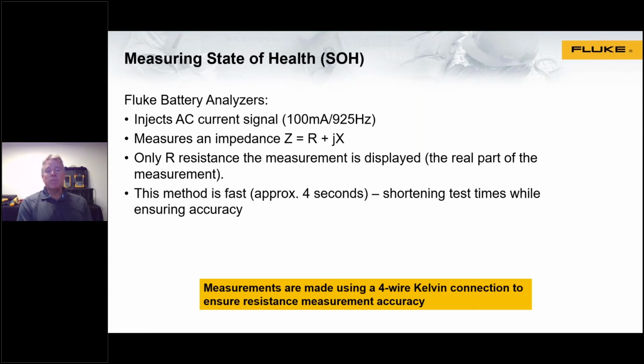It's a fast measurement technique, so per cell, it's about 4 seconds. So it shortens test times while ensuring the right measurement and accuracy. Now, in order to do that, we need to make a measurement which is called a 4-wire Kelvin connection. You might not be familiar with that, so we'll take a deeper look at what that is and why you need a 4-wire measurement.